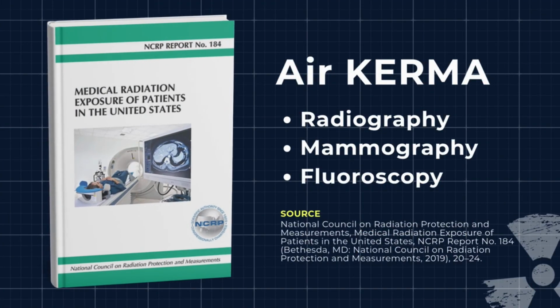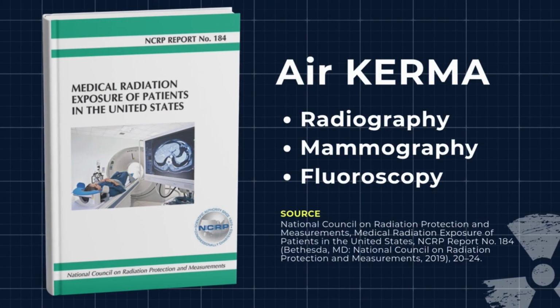Air KERMA is useful when evaluating X-ray tube output, scatter radiation, leakage radiation, and the radiation incident on or near the patient. It also appears in modern fluoroscopic and radiographic dose metrics. The NCRP Report Number 184 includes air KERMA-based quantities among the recommended metrics for medical imaging procedures.